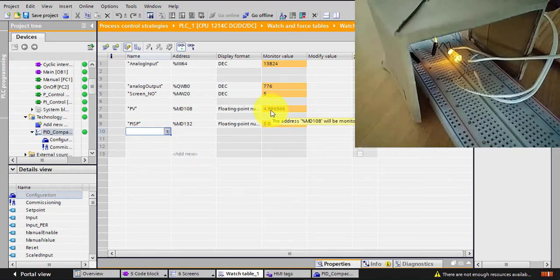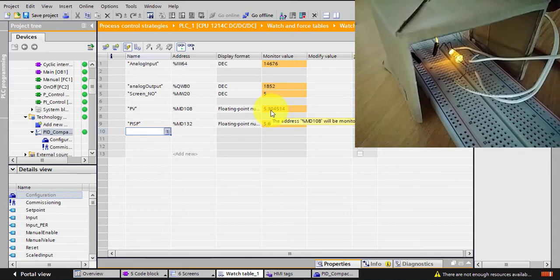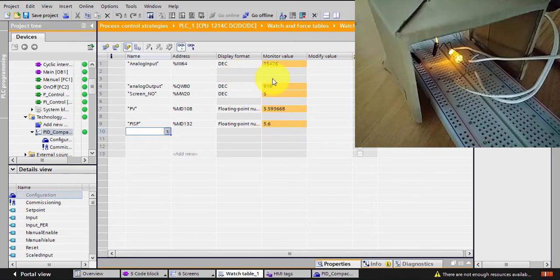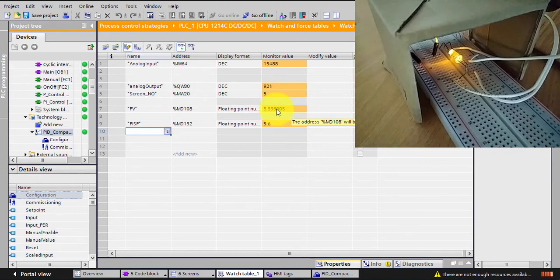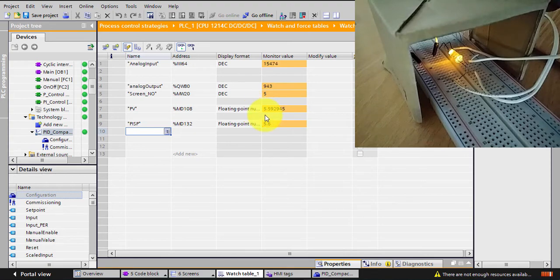I'll change the setpoint to 5.6. The PID Compact changes the analog output so it will go to 5.6, and you can see it responds right away. Looking at the trend, you can see it's directly following — converging to the new setpoint.